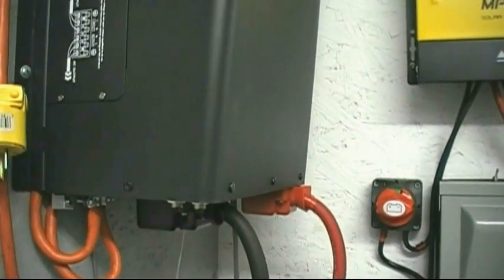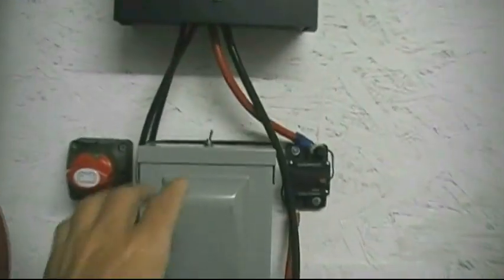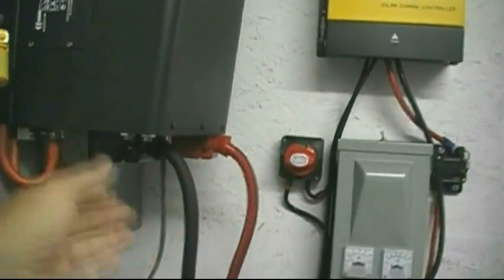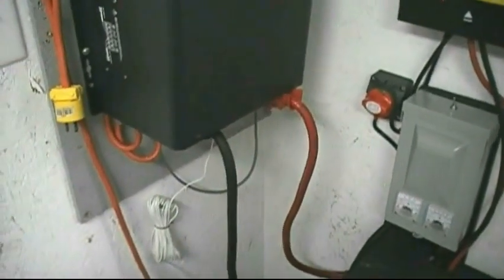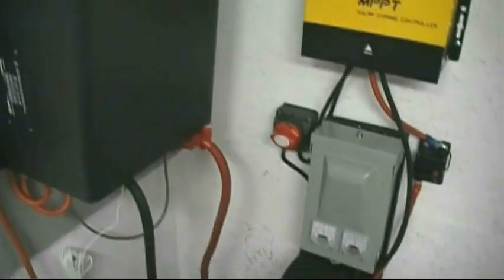This isn't just an inverter — it's also a charger. So on one of those 15-day cloudy stretches where the batteries aren't being fully topped off by solar, I can flip the switch and see the current going back to the system to charge the batteries, while monitoring to make sure nothing's getting out of hand. It has a variable current adjustment — I've got it set around 8 to 10 amps. When you're charging batteries, especially while not drawing off them, you don't want to cook them with high current. A slow charge of 8 to 12 amps over a longer period is more than enough.